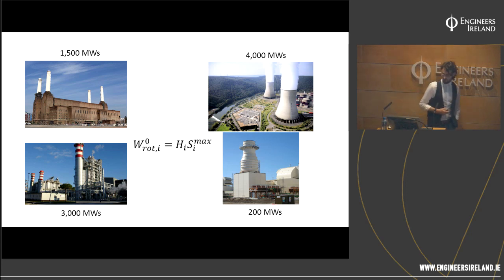And the reason I throw up this equation is because a nuclear plant is on average heavier than a CCGT because it has such a great electrical size. You're talking about 1,000 MVA for a nuclear plant, but its inertia constant is lower than a CCGT. You're talking 500 MVA for a combined cycle gas turbine, but its inertial constant is at least 6 for a single shaft. For a double shaft CCGT, that goes higher again. So these plants range for different reasons.